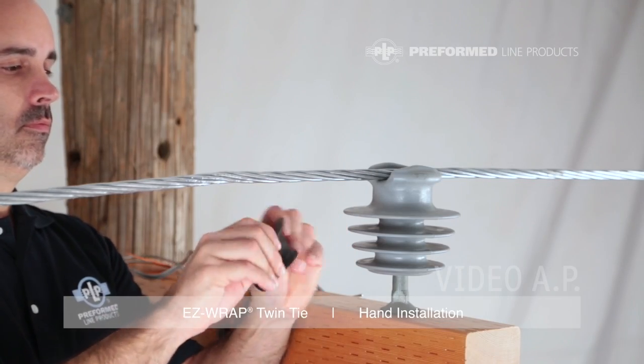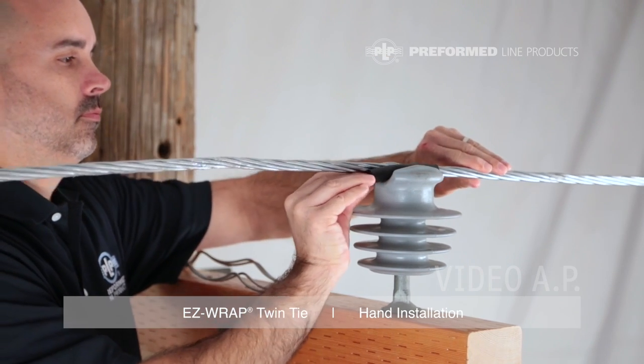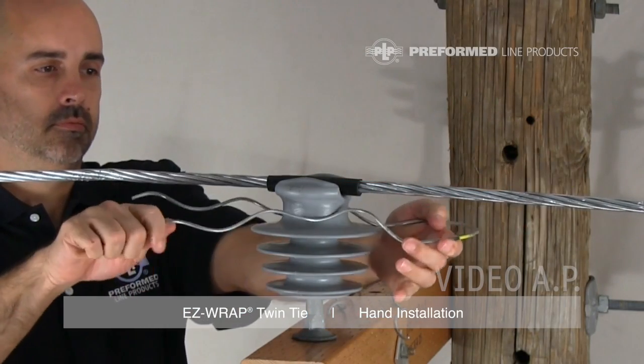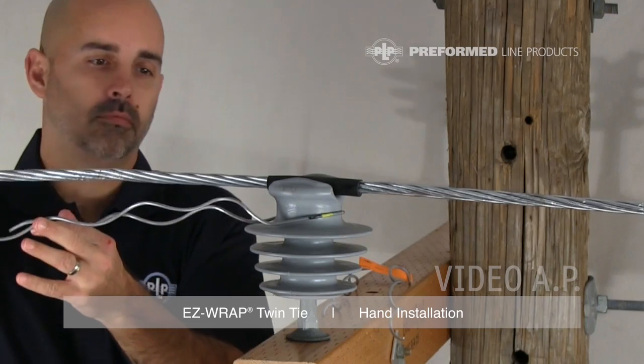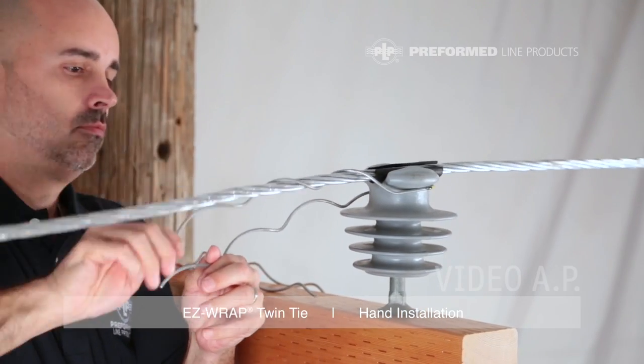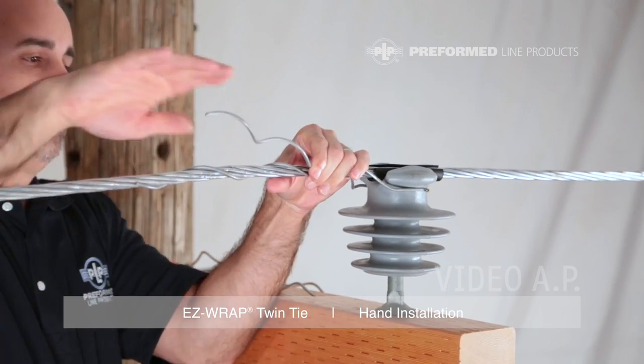Install the tie tube onto the conductor with the slit facing away from the insulator. With the first crossover mark in the upright position, install half of the EZ-WRAP Twin Tie around the neck of the insulator. Begin wrapping the leg starting with the crossover mark on top of the conductor. Wrap this leg to completion by snapping the leg end into place using thumb pressure.